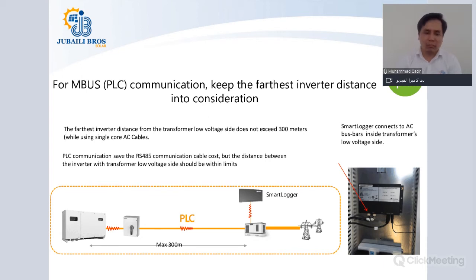So our smart loggers can support this, and in case of any query where you have a specific project, please discuss that. But meanwhile, please make sure that your distance for the single-core cable is around 300 meters, and for the multi-core cable, it can go up to 500 meters, because signal distortion is not a big problem in that case.